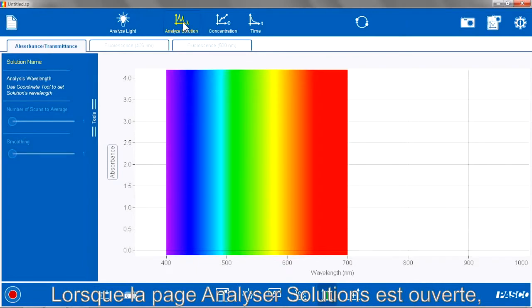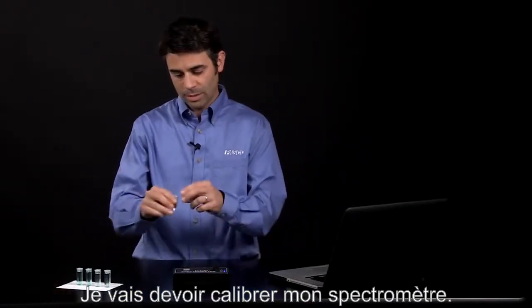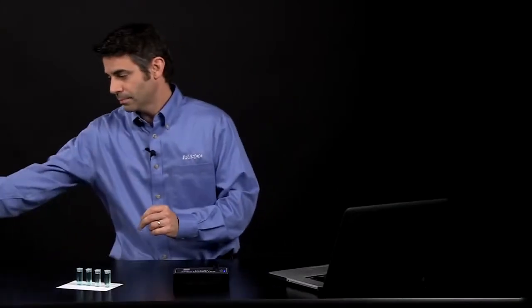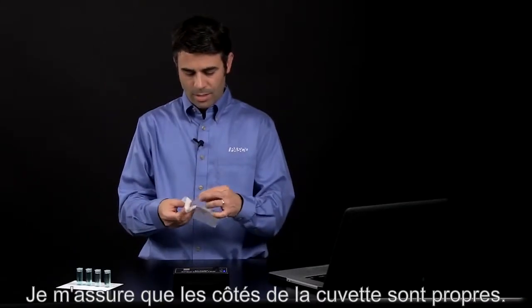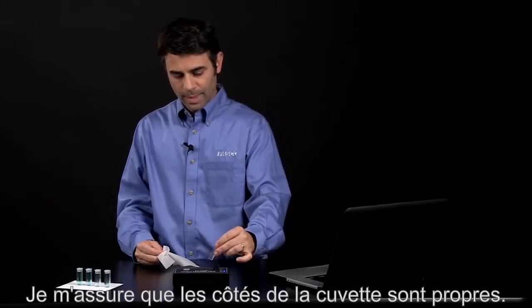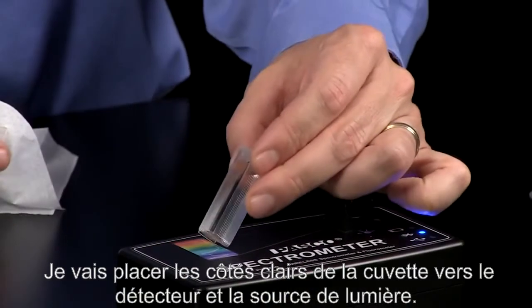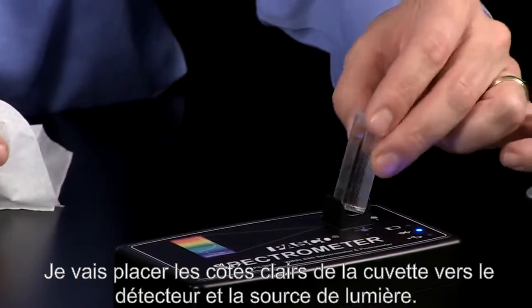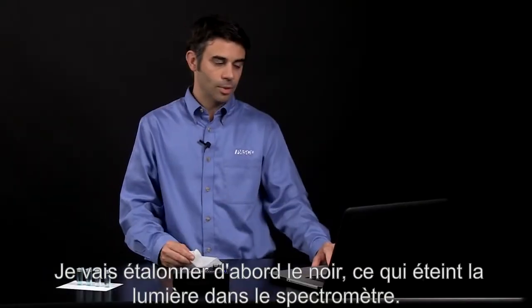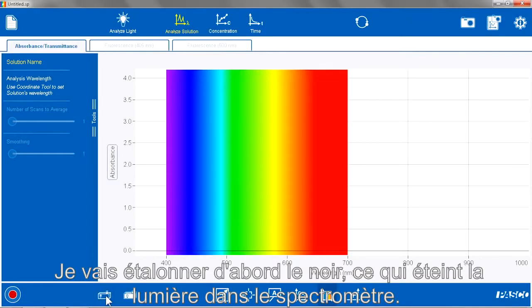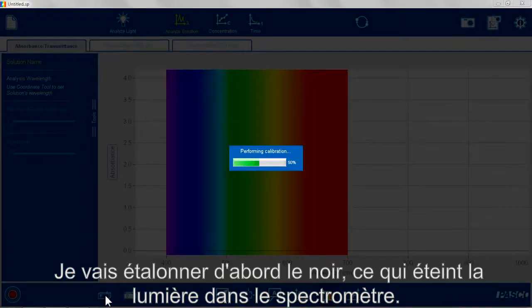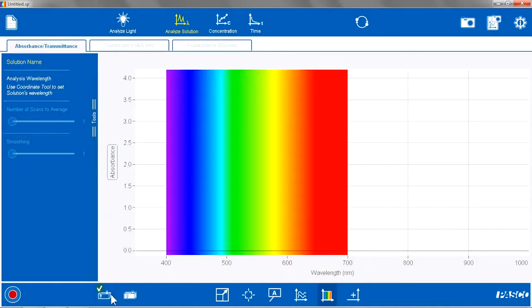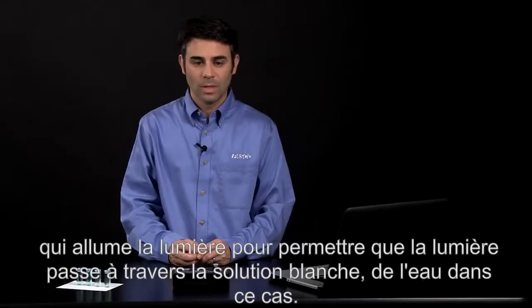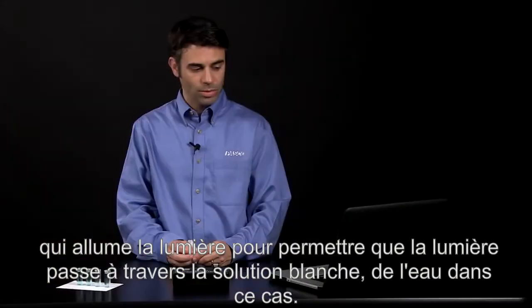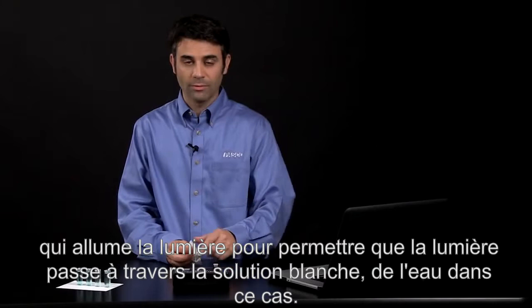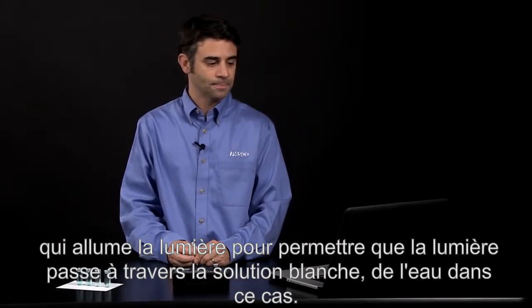Once the Analyze Solutions page is up, I'm going to have to calibrate my spectrometer using a blank. So I'm going to make sure the sides of the cuvette are clean. I'm going to put the clear sides of the cuvette towards the detector and the light source. And I'm going to blank my cuvette using a dark reference, which turns off the light in the spectrometer, and a light reference, which turns on the light to allow all that light through the solution, or through the solvent in this case, of water, the blank solvent.